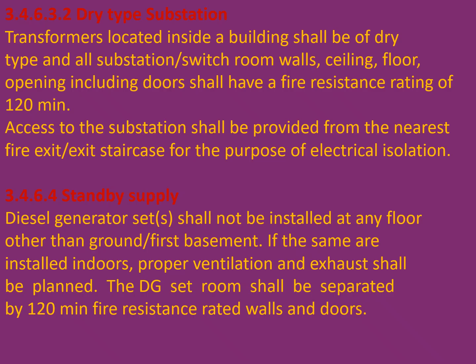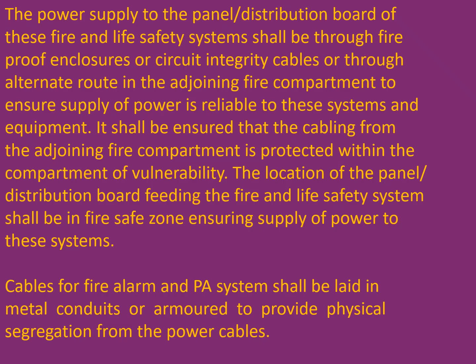In case of standby supply, that means diesel generator rooms, shall not be installed at any floor other than ground or first basement. If the same are installed indoors, proper ventilation and exhaust shall be planned. The DG set room shall be separated by 120 minute fire resistance rated walls and doors. Friends, we are discussing firefighting provisions to be made in substations.